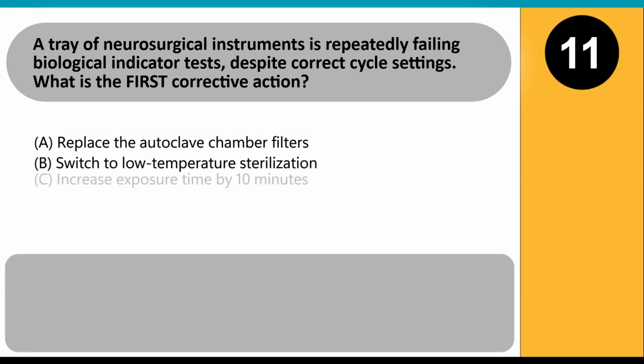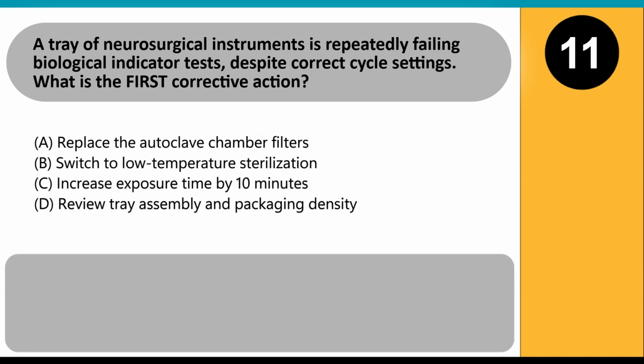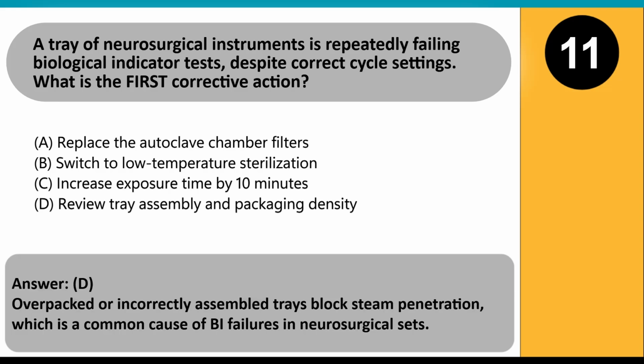A tray of neurosurgical instruments is repeatedly failing biological indicator tests, despite correct cycle settings. What is the first corrective action? A. Replace the autoclave chamber filters. B. Switch to low-temperature sterilization. C. Increase exposure time by 10 minutes. D. Review tray assembly and packaging density. Answer: D. Overpacked or incorrectly assembled trays block steam penetration, which is a common cause of BI failures in neurosurgical sets.